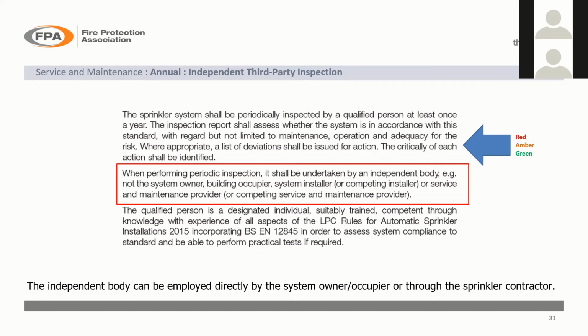The reason is that, first of all, as a contractor, you can't mark your own homework, because if you put a system in and you put it in wrong, you're really not going to flag that up. Everybody makes mistakes, but you can't really mark your own homework. The other thing is that if you're inspecting the work of others and you're commercially trying to win their work, then you've got a vested interest in painting it blacker than it needs to be in the report for your own commercial ends, whereas an independent third party doesn't have those financial incentives and can look at it with a clean slate, as it were. So it's very important that this annual third party inspection is carried out by an independent third party, and it can't be carried out by any of those people.